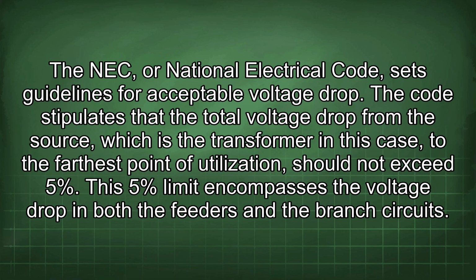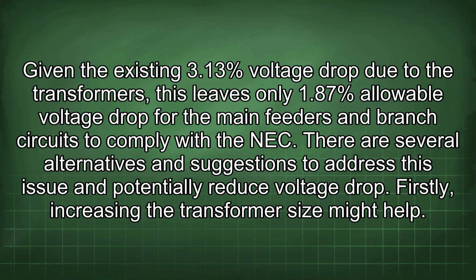The NEC, or National Electrical Code, sets guidelines for acceptable voltage drop. The code stipulates that the total voltage drop from the source, which is the transformer in this case, to the farthest point of utilization, should not exceed 5%. This 5% limit encompasses the voltage drop in both the feeders and the branch circuits. Given the existing 3.13% voltage drop due to the transformers, this leaves only 1.87% allowable voltage drop for the main feeders and branch circuits to comply with the NEC.